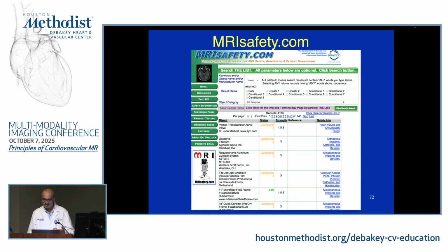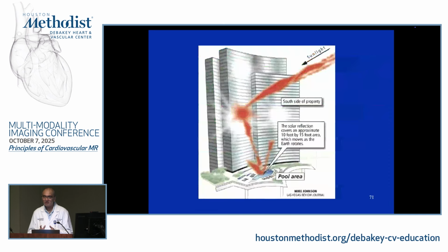And the point of that is, when we talk about how we label a device, we don't say MRI safe or unsafe. We say it's conditional, in the sense that there's a series of scenarios that we've tested and we've shown at least reasonable safety. It doesn't mean you can't possibly think of every possible scenario. The other thing is you can't possibly test every possible scenario.